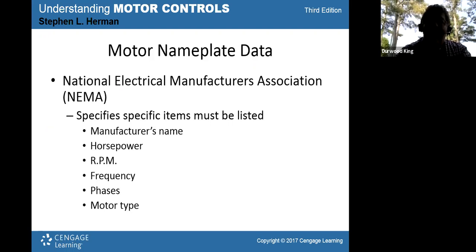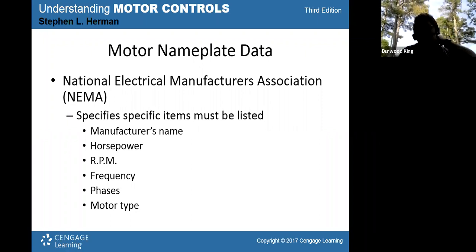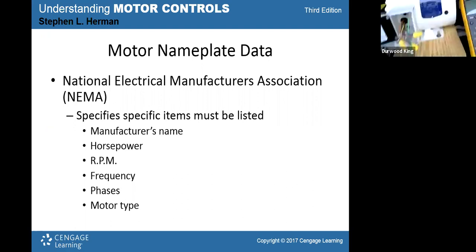Okay, your nameplate data, which is standardized by NEMA. NEMA in the U.S. is the National Electrical Manufacturers Association, and they have standards that a lot of companies agree to stick with. So there is some kind of standardization in the U.S. on data that's on nameplates for motors. And I'm going to move the webcam just for a second over to this motor right here. And do you see that nameplate there in my webcam?